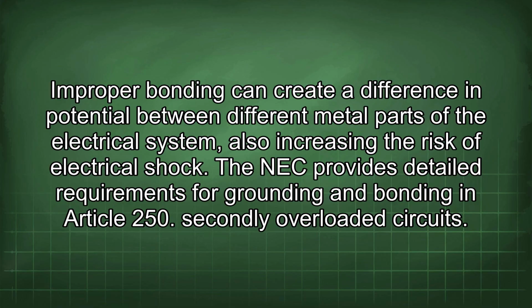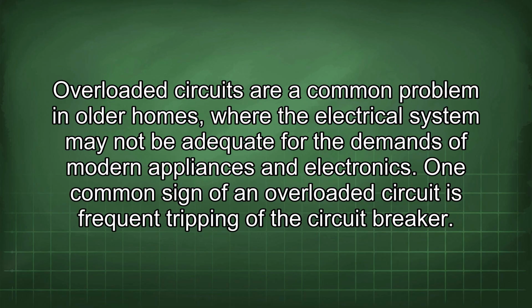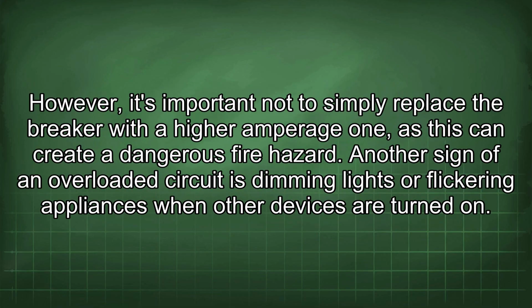Secondly, overloaded circuits. Overloaded circuits are a common problem in older homes, where the electrical system may not be adequate for the demands of modern appliances and electronics. One common sign of an overloaded circuit is frequent tripping of the circuit breaker. However, it's important not to simply replace the breaker with a higher amperage one, as this can create a dangerous fire hazard. Another sign of an overloaded circuit is dimming lights or flickering appliances when other devices are turned on.